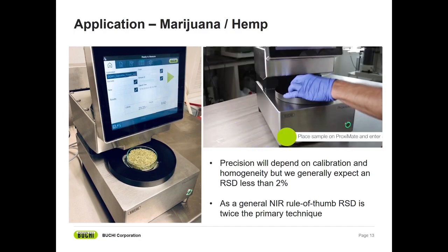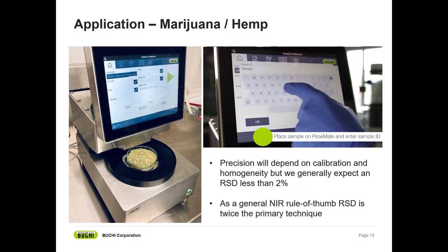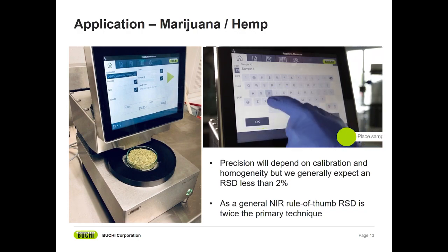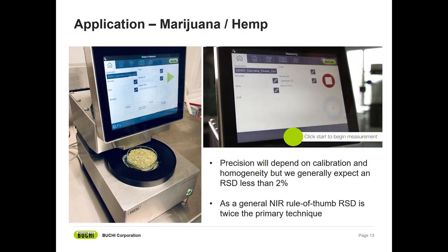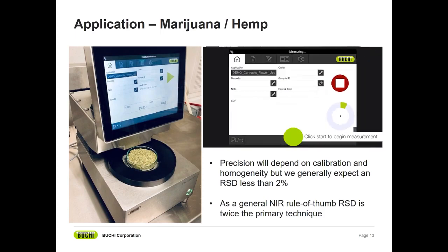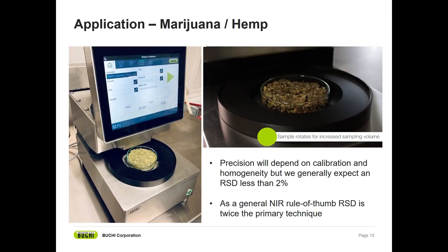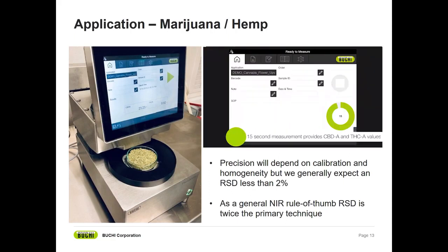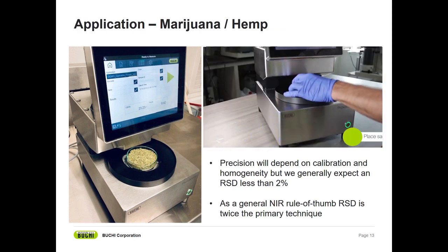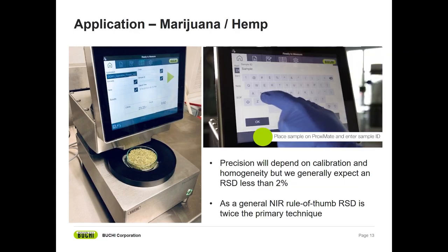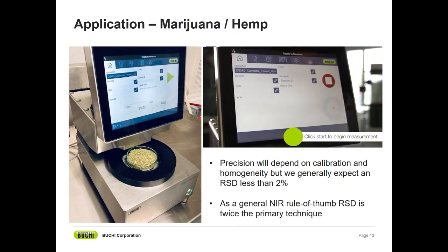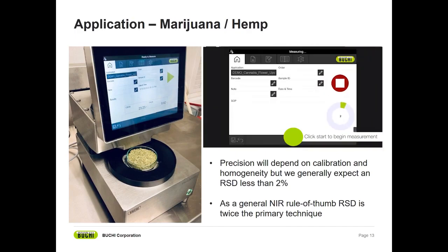I like to grind the flower directly into a petri dish, wipe the bottom of the petri dish just to ensure it's clean, and then set the dish directly on the instrument. 15 seconds later, I'll have a result. A common question we always get is what to expect on the precision and accuracy. Accuracy will always come back to the calibration and quality of reference materials that you use to create your calibration. Precision will come down to your consistency in sample preparation and the concentrations. The closer we get to zero in concentration, the larger the precision will be.